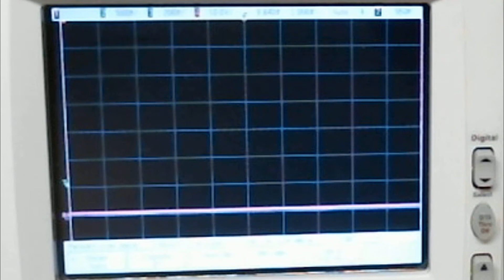Now we're going to simulate a cold starting situation. Under the cold starting situation, the cold start switch will be grounded, which will prevent the device from switching into closed loop. The oxygen sensor signal is 0 because the oxygen sensor is cold. So we'll start the device and it will operate at the fixed duty cycle of 40%, which is what it should be set for in order to warm up in a rich condition.